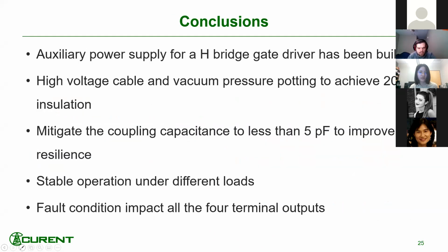And for conclusions and future work, the conclusion is that an auxiliary power supply is built, and we use vacuum pressure potting to achieve the 20 kV insulation, and the coupling capacitance is less than 5 picofarad to improve the EMI immunity, EMI resilience, and also operation under different loading conditions. I think that's all from me today, and I probably ran out of time a little bit.